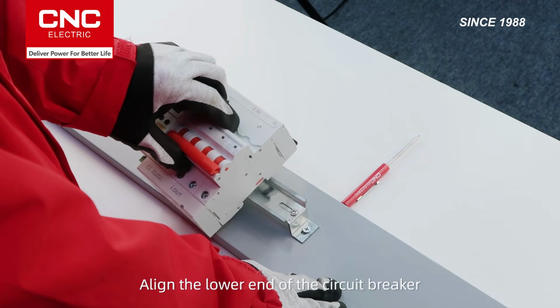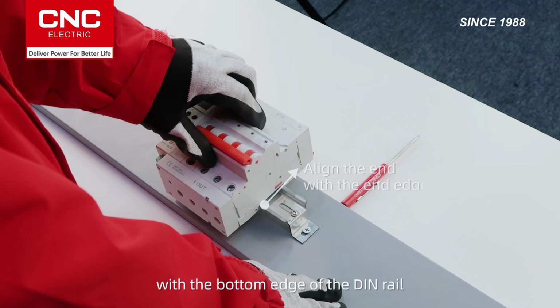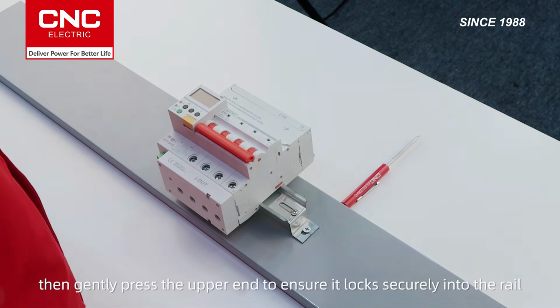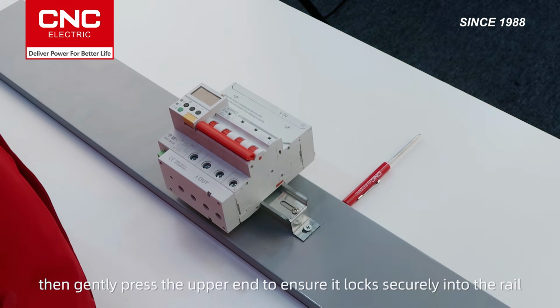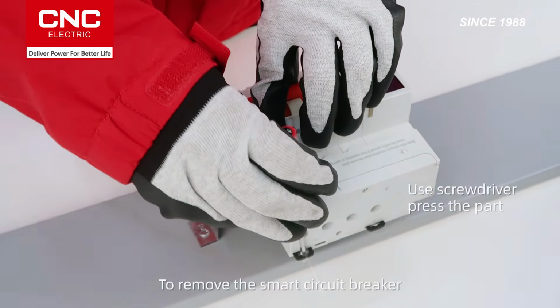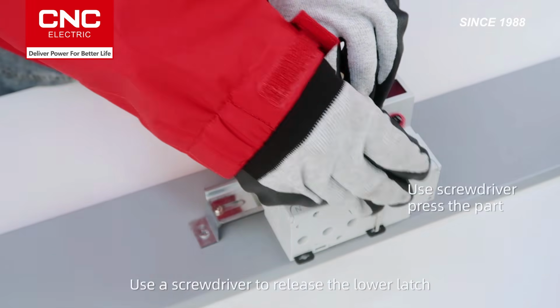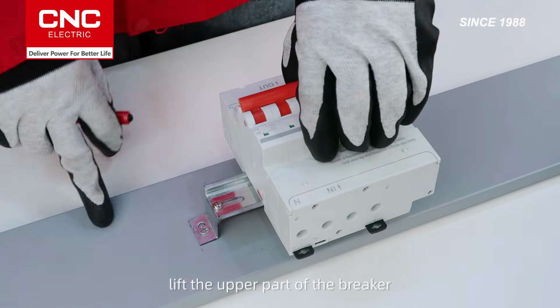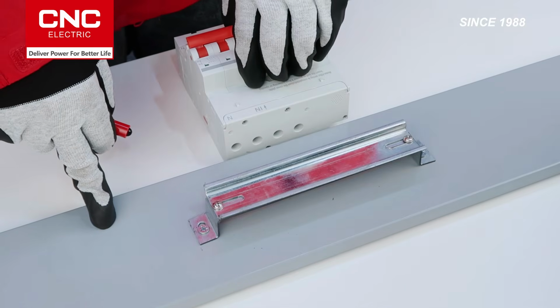Installation tips: align the lower end of the circuit breaker with the bottom edge of the DIN rail. Then gently press the upper end to ensure it locks securely into the rail. To remove the smart circuit breaker, use a screwdriver to release the lower latch. Lift the upper part of the breaker, then remove it.